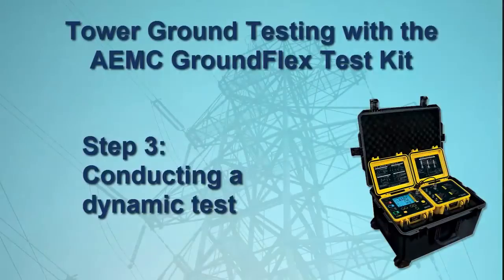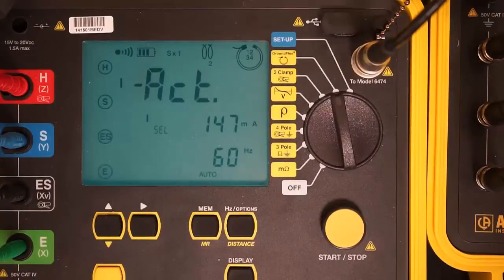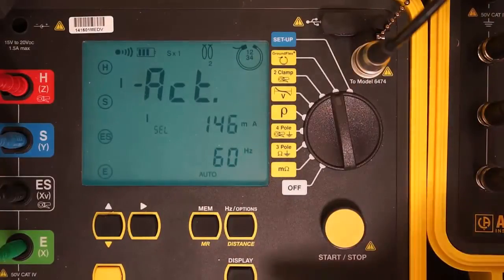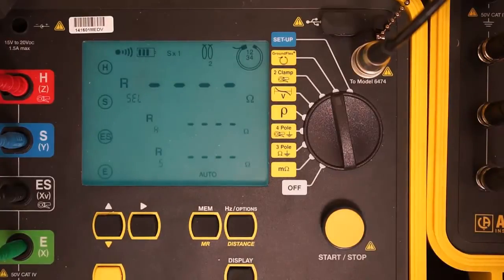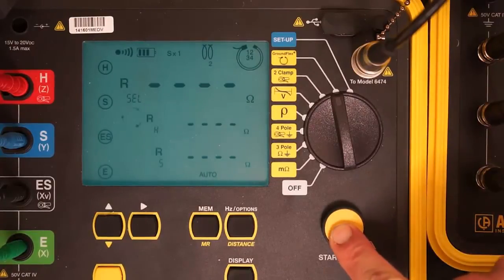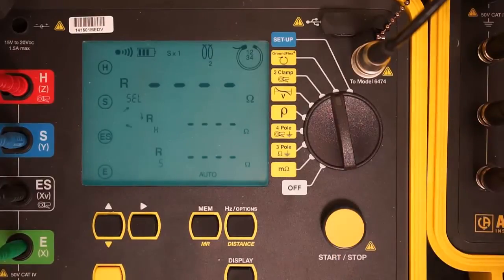Now that we have obtained static measurements, we can perform a dynamic test. To do this, press the display button to return to the main display screen. Then press and hold down the Start-Stop button on the Model 6472. When you do this, the instrument will beep once. Continue to hold down the button until the instrument beeps a second time, and then release the button. The instrument now performs a test using a test voltage of 32 volts and a frequency of 128 Hz.